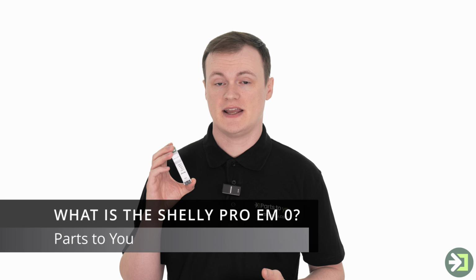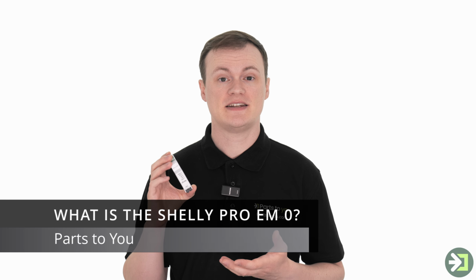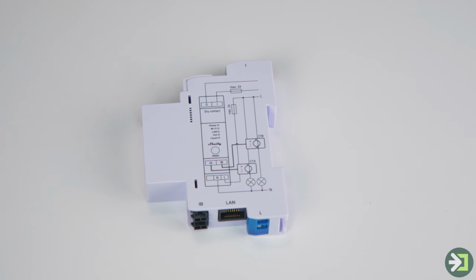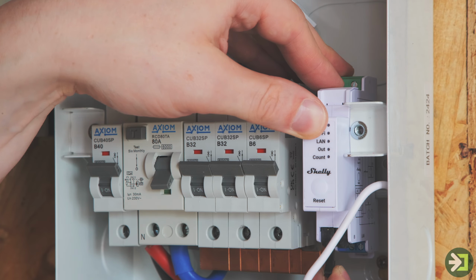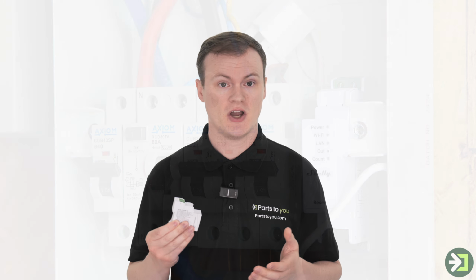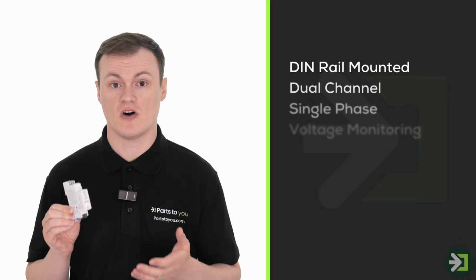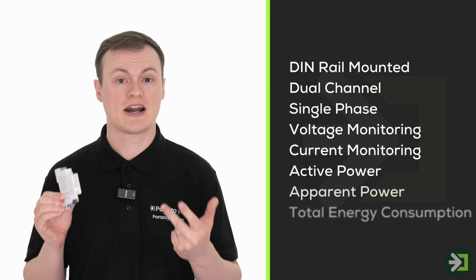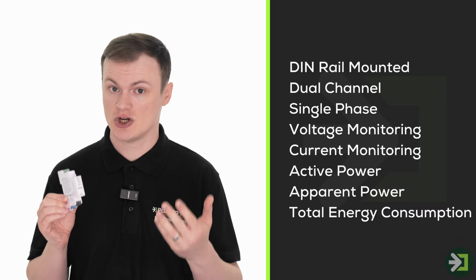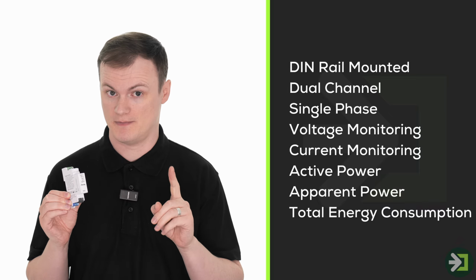The Shelly Pro EM 50 amp sits in a very different category to plug-in smart meters or retrofit clamps. This is a DIN rail device, designed for distribution boards, consumer units, and professional installations where reliability and integration matter more than convenient packaging. At its core, it's a dual-channel single-phase energy meter capable of monitoring voltage, current, active power, apparent power, and total energy consumption in real time.